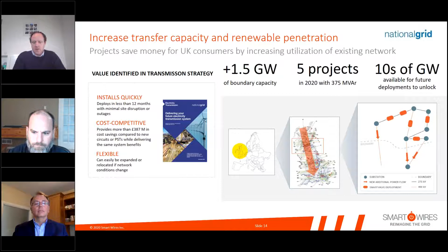National Grid's system has high wind generation in the north of Scotland that needs to be squeezed down through the network to load centers in the south. They're able to optimize this with power flow controllers, optimized pre- and post-contingency to support increased transfers. From a cost perspective, that solution saved National Grid up to 400 million compared with new circuits or PSTs, so the benefits can be delivered quickly and at much lower cost.